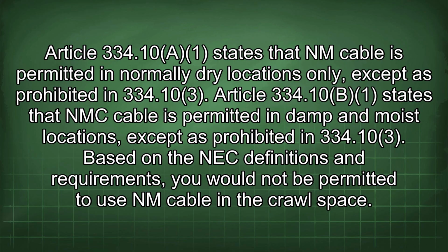Article 334.10(a) states that NM cable is permitted in normally dry locations only, except as prohibited in 334.10(3). Article 334.10(b) states that NMC cable is permitted in damp and moist locations except as prohibited in 334.10(3).